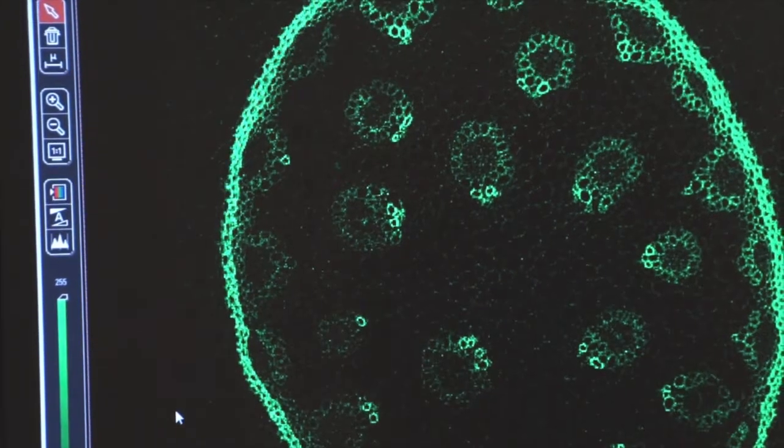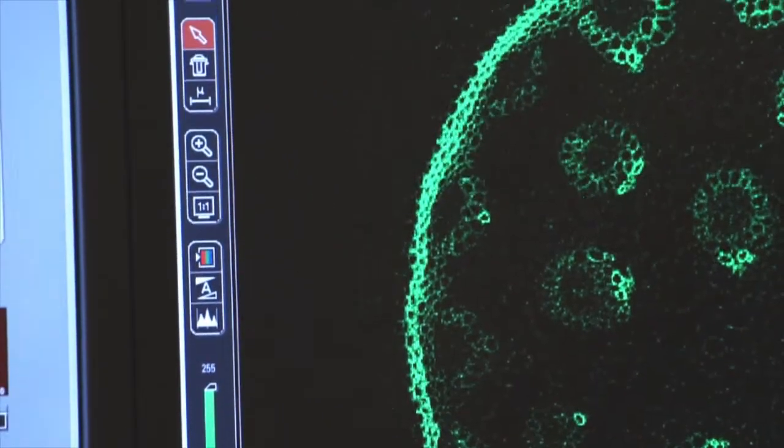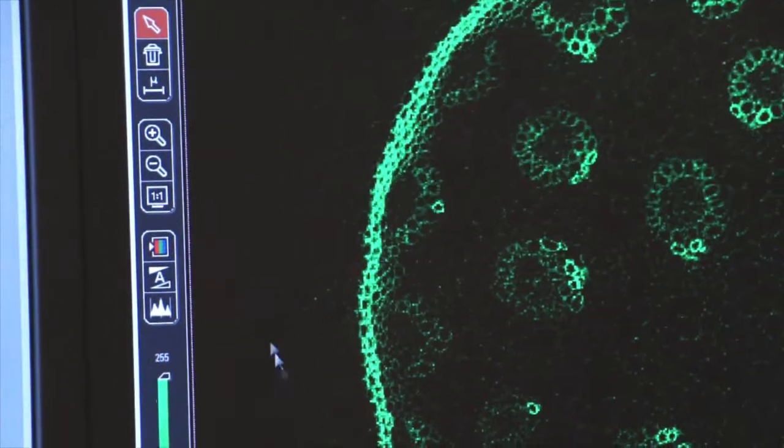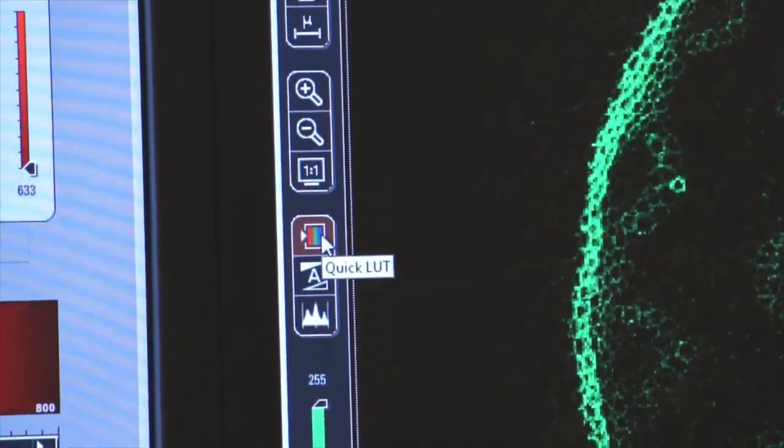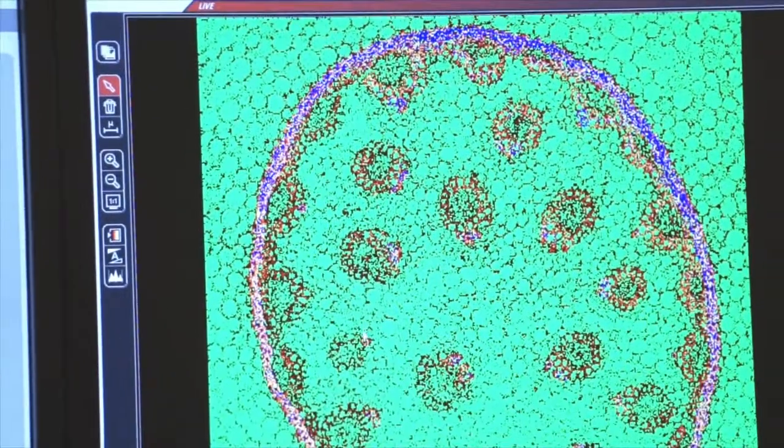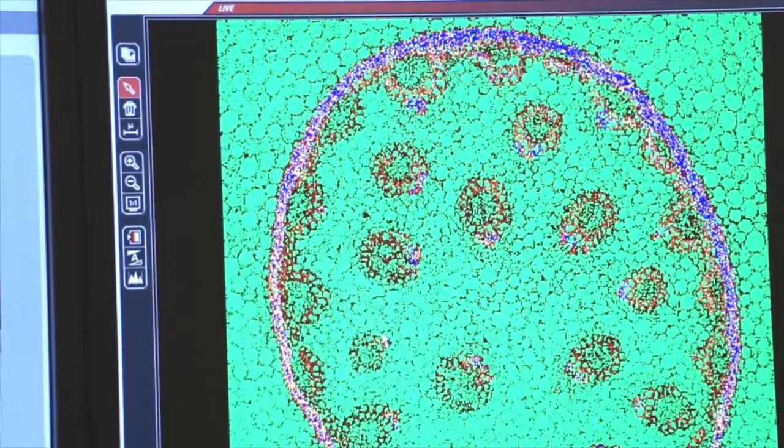We now have a live image on the screen, and I want to show you an easy way to set the gain and offset so your images are the crispest they can be. If you click on this little box here, this is the quick lookup table. You click on it once, it changes the color of your pixels to blues and greens that you can use to identify how your gain and offset should be set.